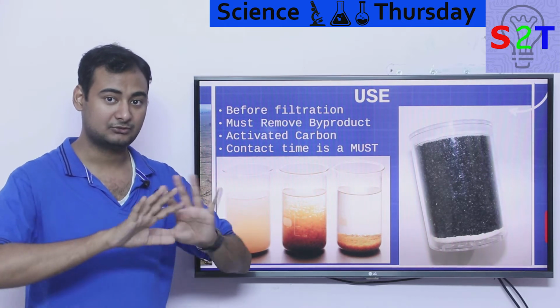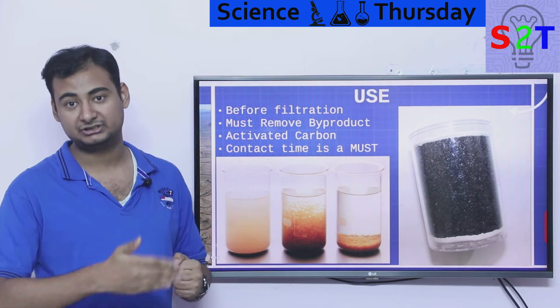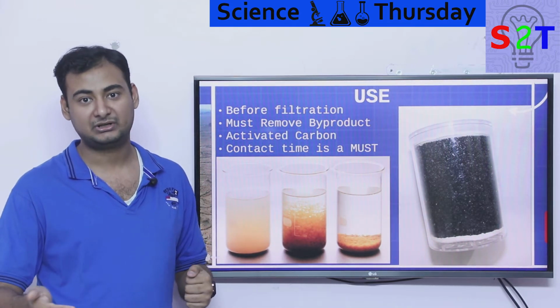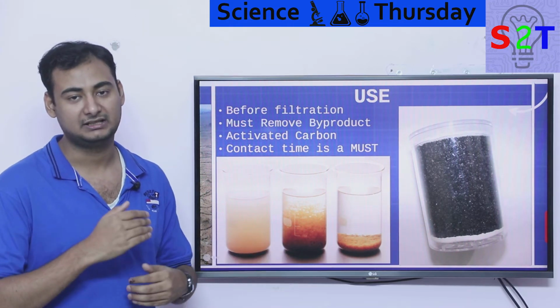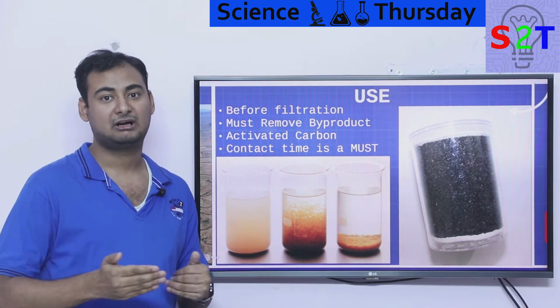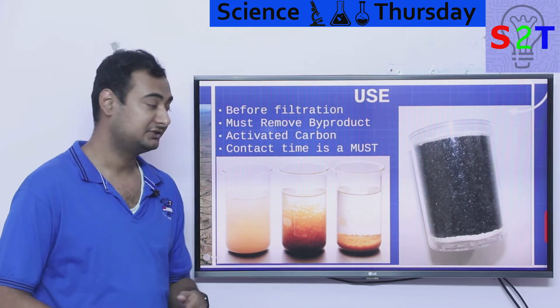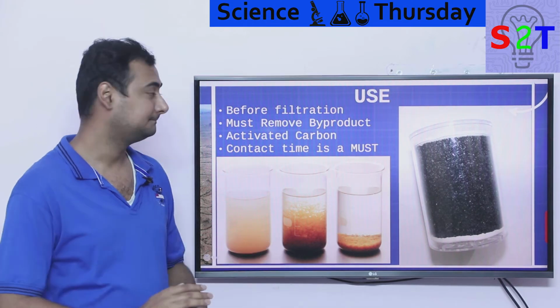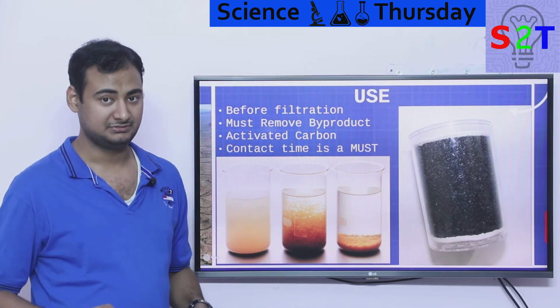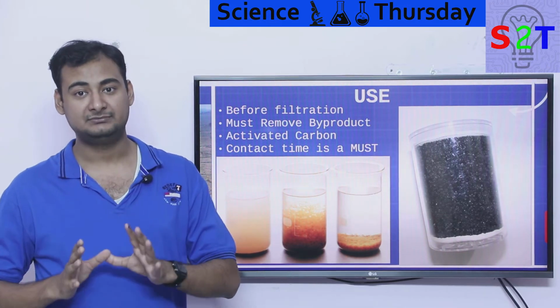You have to give it time to just decompose and chill down, because if you directly feed active O3 into an RO membrane, the membrane will be destroyed. Not destroyed as in it will explode, but the efficiency of your RO membranes will go down, and after a while contaminants will start to pass through. So we have to make sure O3 is given enough time to do its magic, because you don't want to rush it. Basically, in the UV case you have to make sure the exposure is matched. In this case you have to make sure the time is enough.